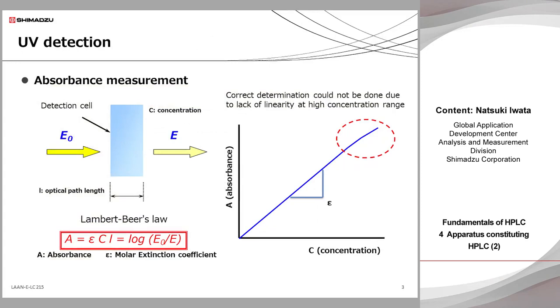When a compound absorbs light energy at a particular wavelength in the UV visible region, the energy of electrons rises from the ground state to the excited state. This is UV absorption. The absorbance detector measures the intensity difference of the incident UV light to the flow cell and the transmitted UV light from the flow cell, which means UV absorption. The detection principle of the UV detector is explained in this slide.